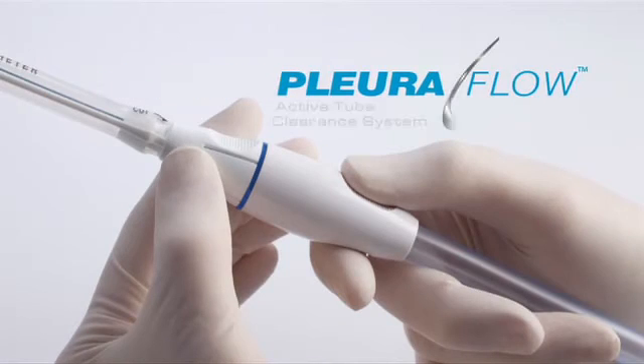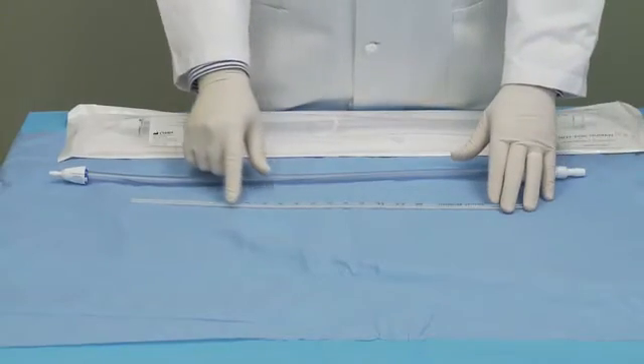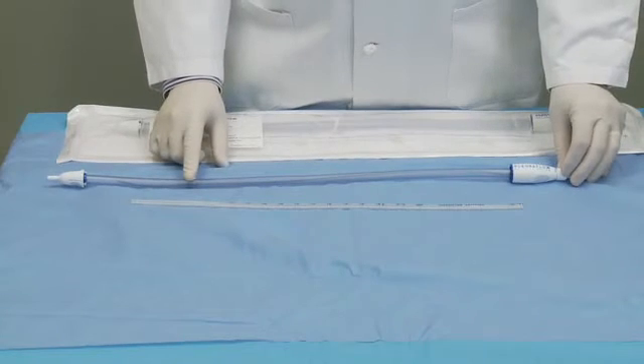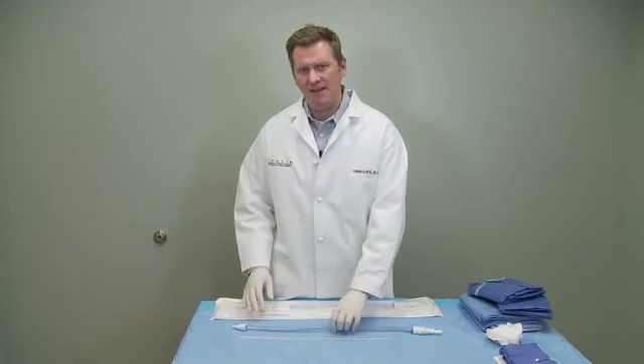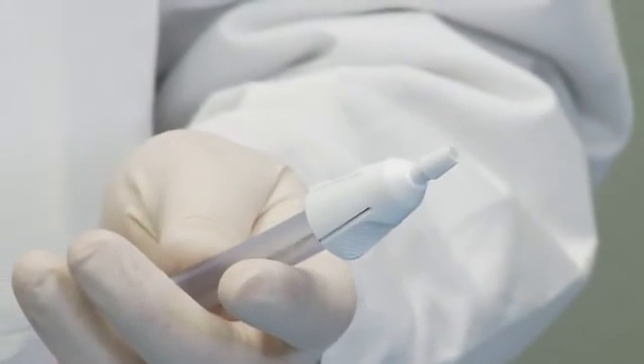To address the problem of chest tube clogging, we developed the PleuraFlow active tube clearance system. The system includes two pieces: a standard silicone chest tube and the guide tube that has the clearance system. The key feature is a guide wire that is advanced in and out of the chest tube to clear it of any obstructions.